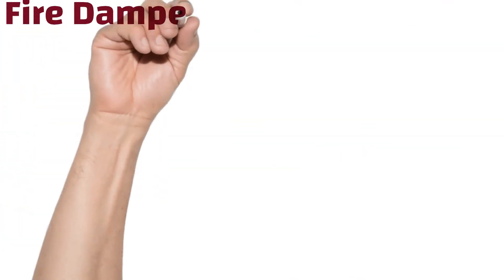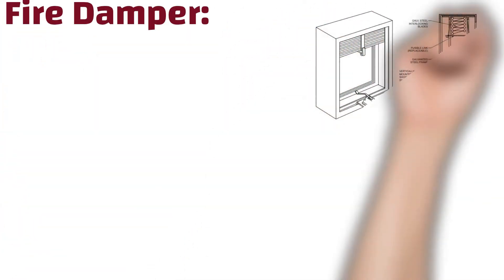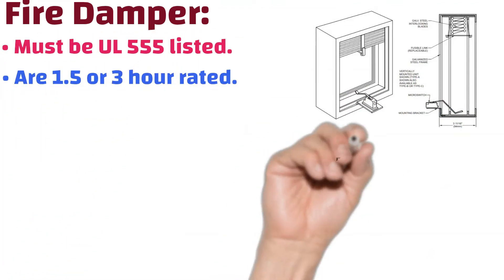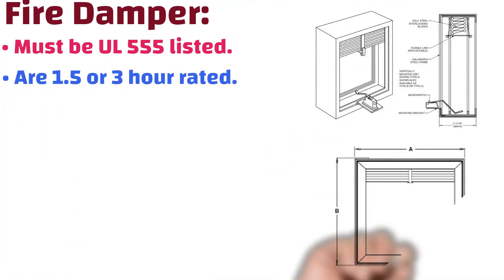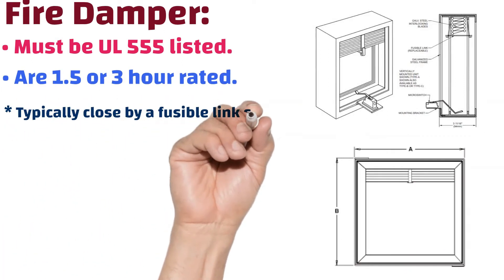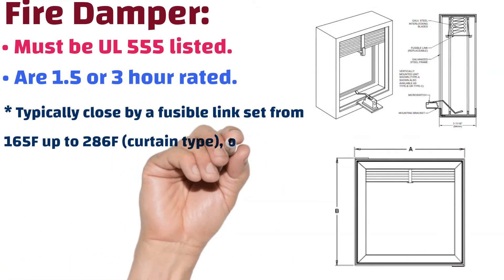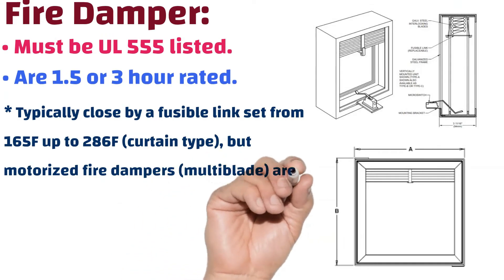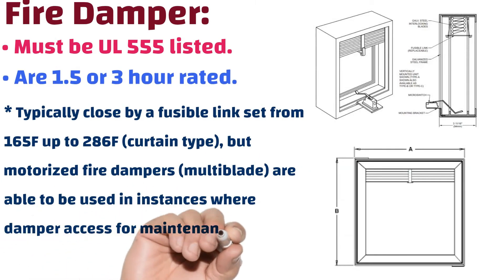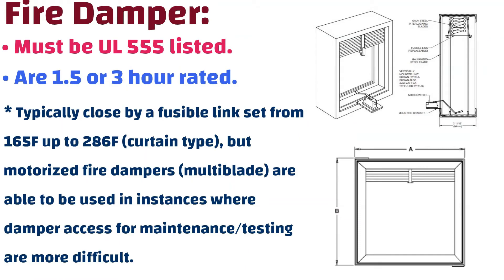Fire dampers must be UL 555 listed and are 1.5 or 3-hour rated, typically closed by a fusible link set from 165 degrees Fahrenheit up to 286 degrees Fahrenheit. Curtain-type dampers, motorized fire dampers, or multi-blade dampers can be used in instances where damper access for maintenance and testing is more difficult.